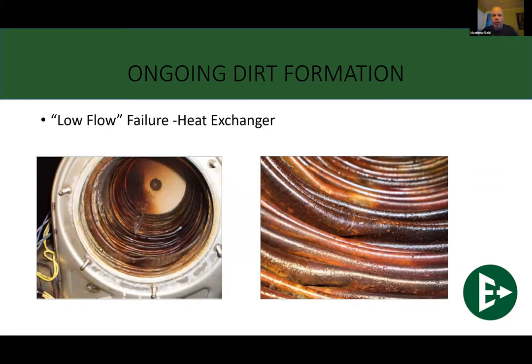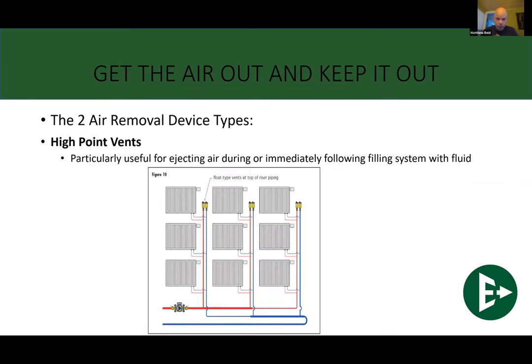By stopping ongoing dirt formations, like I said, all it takes is air and metal that reacts with air. We can't take away the metal that reacts with air, so let's get the air out. There's two basic types of air removal devices inside of your system. There's your high point air vent, really good for doing your system fills. They automatically vent the air out. When the water gets up to the top, the float comes up and stops them. And again, essentially they are sealed. They work great the first time. They usually work the second time, and then they start to have diminishing returns the more times that we ask them to do that autofill system.